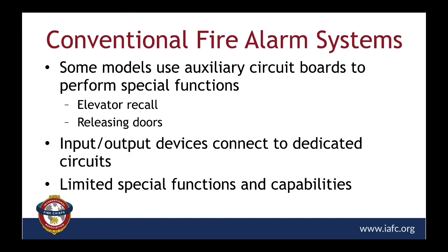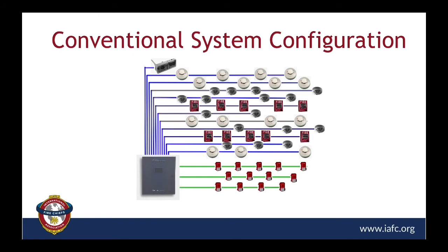Now, another part of the conventional system that's important for us to realize is that these things not only receive pull stations and smoke alarm notifications, and make some noise with the horns or bells attached, but they also have additional relays installed within them that operate other parts of the building, such as elevator recall. It could be for releasing doors, releasing fire doors, or interconnecting to a security system to unlock certain aspects of the building. So it's important to realize that they do have these auxiliary functions, but as we're going to see in the next slide, what's really key to these is the input and output devices that are connected via dedicated circuits. And here we go, Chief.